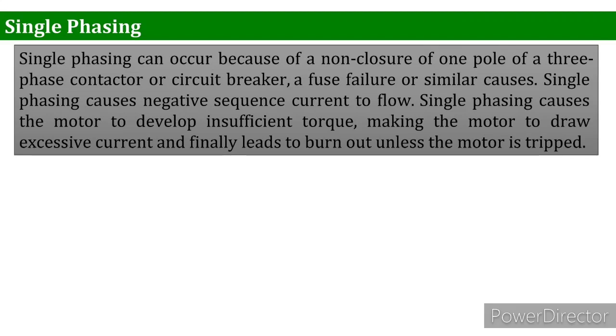There is a thermal limit on the amount of negative sequence current that can be safely carried by the motor. As we all know, the heat liberated due to the negative sequence current we can write as I square T, because it is a power loss. So we can use a relay which can detect the negative sequence current. When a negative sequence current is detected, we can also check whether single phasing has occurred or not.